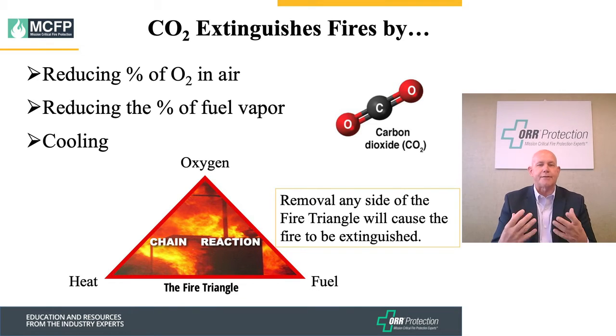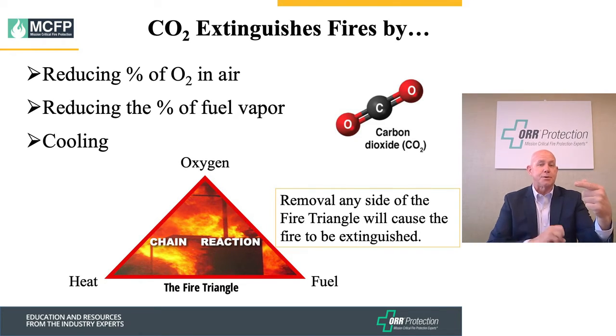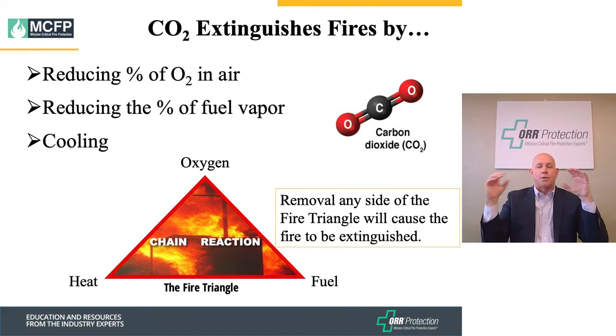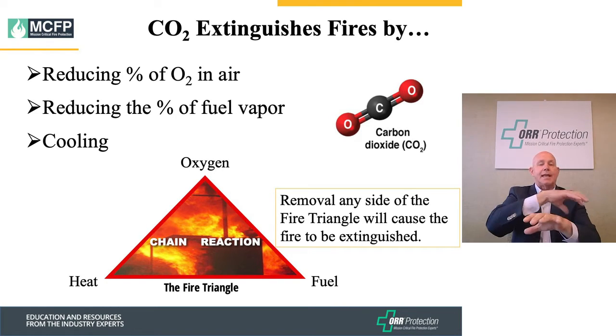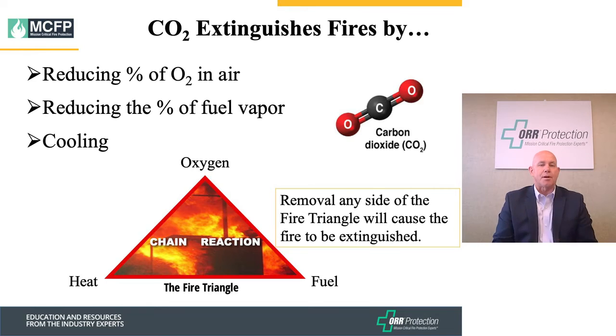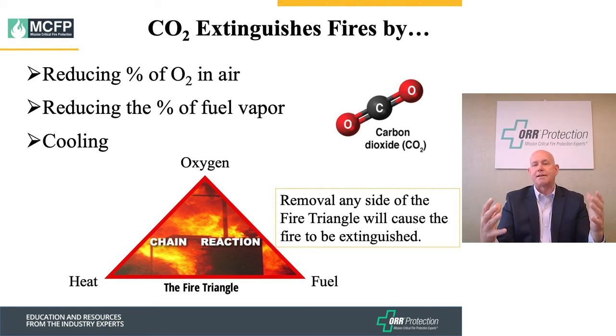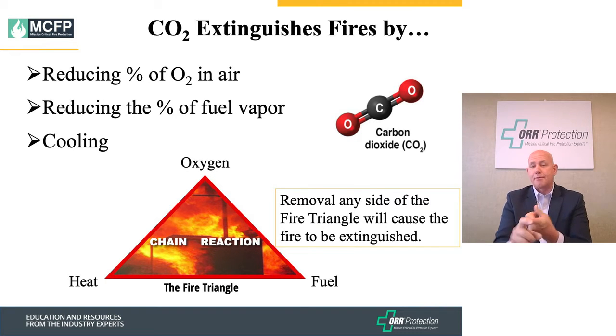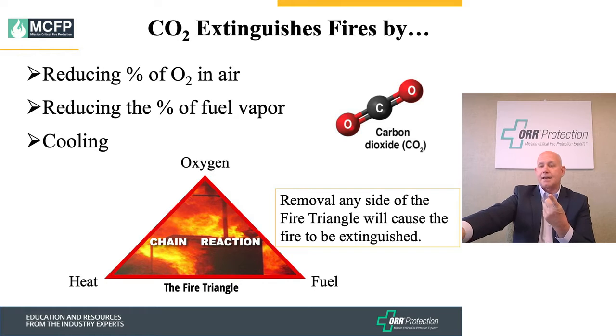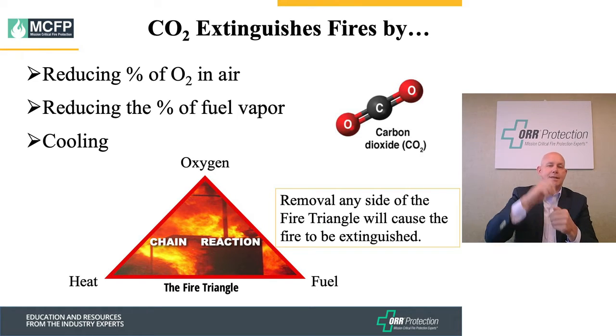CO2 has some very unique properties. It can reduce a fire by displacing oxygen, and it can actually reduce fuel vapor in the air because when it discharges, it displaces and contains the fuel vapor through its molecular structure. CO2 is also dry ice, so it actually cools the environment as well. It can remove the heat side of the triangle by cooling, and it can also displace oxygen.